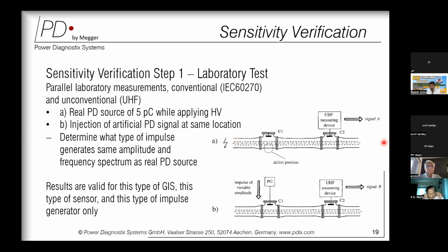If a portion of a GIS has been selected by the manufacturer, they would place the sensors on that portion of the GIS, and just under the sensor, they will inject an artificial partial discharge defect, which in most cases is a moving or floating particle, and apply high voltage to this GIS, and the high voltage will be raised. Now two parallel measurements are happening. One is the conventional measurement, where we measure the discharge in picocoulombs, and the second is the UHF measurement, where we measure the voltage captured by this UHF sensor.